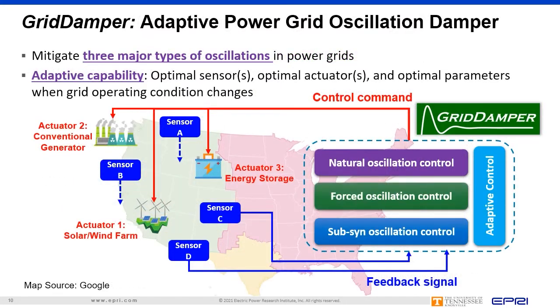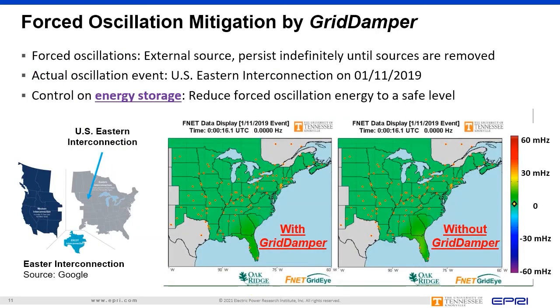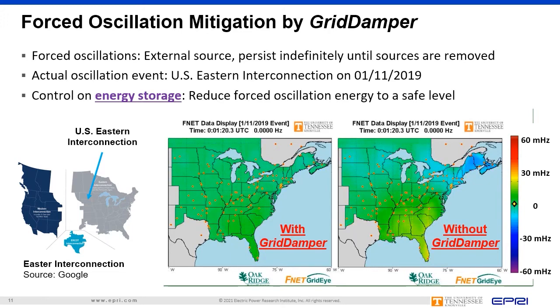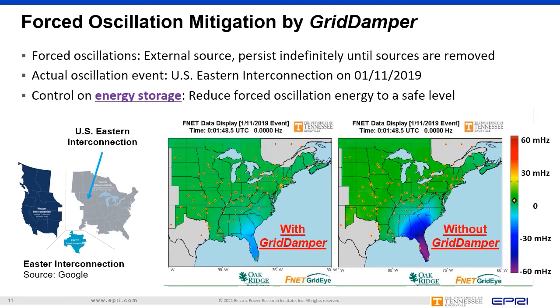Grid Damper also detects and controls forced oscillations. In the U.S. Eastern Interconnection, an oscillation event happened in January 2019 with a driving source in Florida. Based on simulations, Grid Damper was able to quickly detect the forced oscillation and execute fast control over energy storage facilities to greatly reduce oscillation energy to a safe level. This prevents equipment like generators from damage and allows the grid operator sufficient time to locate and remove the driving force.